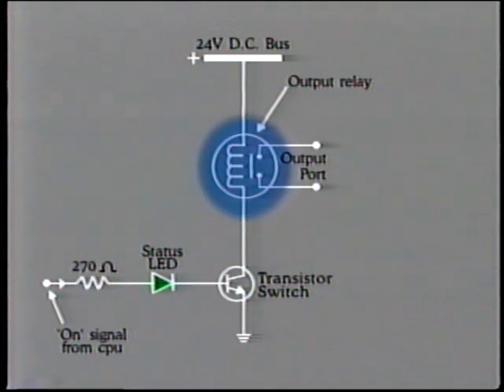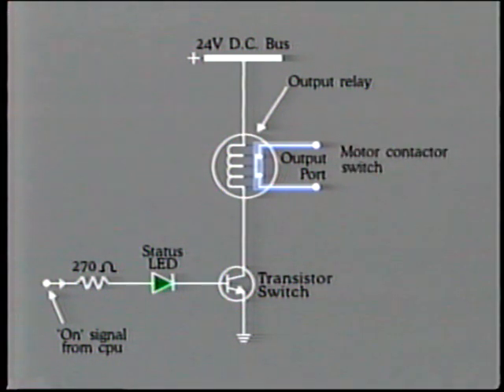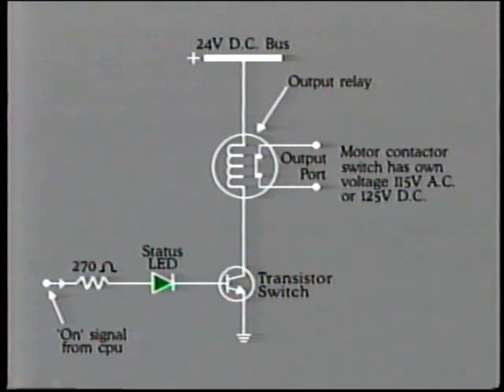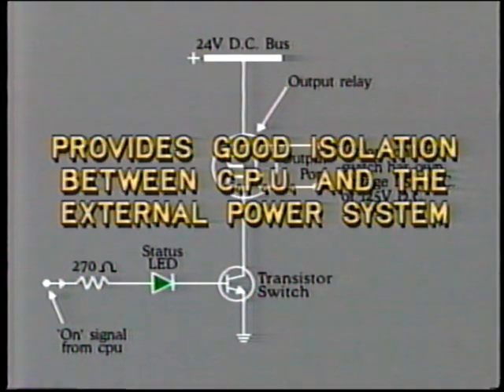When the relay coil is energized, its contacts close, and this completes the external circuit, which in this case operates a solenoid to close a motor contactor switch. The operating voltage for the solenoid is provided from the contactor itself. The PLC relay merely completes the circuit. The operating voltage will probably be 115 volts AC, or perhaps 125 volts DC. This type of output arrangement provides good electrical isolation between the CPU and the external power system.